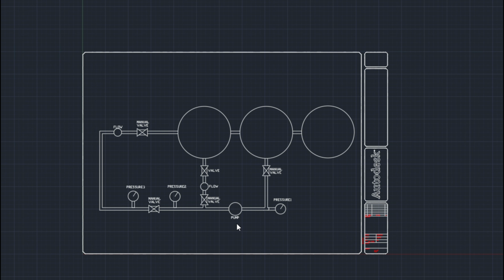Then it's going to keep a steady frequency. We are also going to be using a PID for the flow meter, using the flow meter as the process variable, and we're going to keep the valve as the output. So if we want to keep a 3 gallon a minute level, we're going to either increase or decrease how open the valve is. So if the valve is 100% open and we are trying to get 6 gallons a minute and we're actually at 12 gallons a minute, we are going to decrease the opening of this valve until it reaches the flow meter set point that we want.